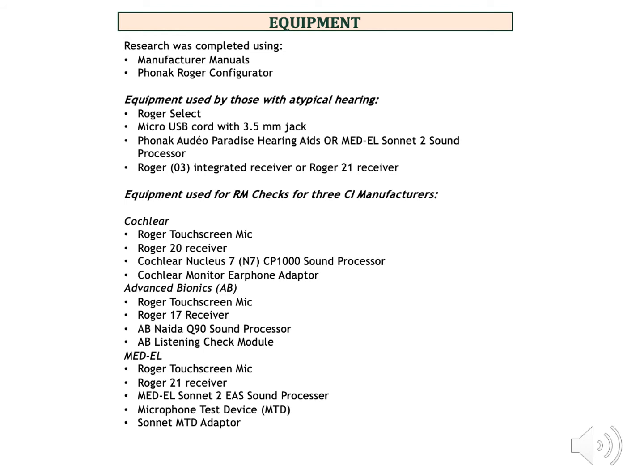The listening checks were also carried out with the typical equipment that you would use to carry that out, but I broke it down into Cochlear, Advanced Bionics, or MED-EL. So for Cochlear, a Roger touchscreen mic was utilized, a Roger 20 receiver was utilized, Cochlear Nucleus 7 CP1000 sound processor, and a Cochlear monitor earphone adapter was used. For Advanced Bionics, we used a Roger touchscreen mic, a Roger 17 receiver, the Advanced Bionics Naida Q90 sound processor, and the Advanced Bionics listening check module was used. For MED-EL, a Roger touchscreen mic, a Roger 21 receiver, a MED-EL Sonnet 2 EAS sound processor, the microphone test device, and the Sonnet microphone test device adapter was utilized.